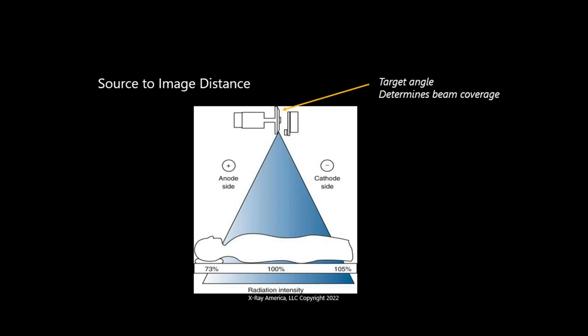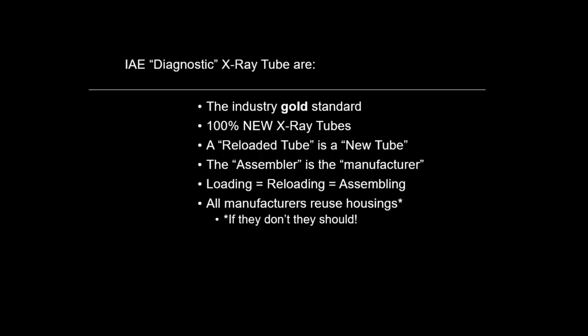Make sure that you get enough dose. One thing when you're working with a system like a LINAC, where you want to have a long SID, you have to have enough dose. You need to use a much bigger tube, with high enough energy to produce enough dose, because the distance is long. Yes, because distance is longer, and it's an inverse square.